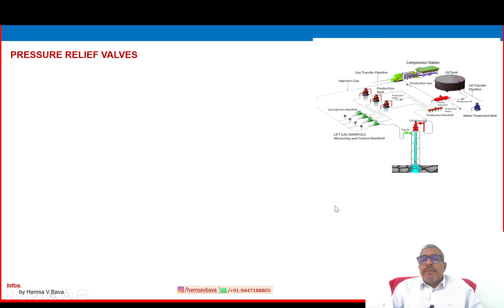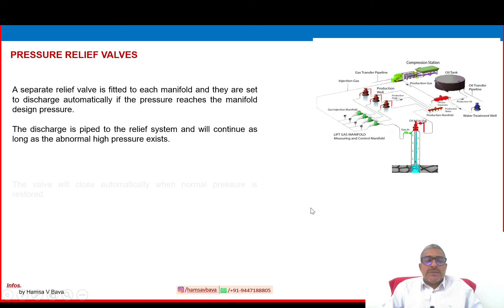Another one is the pressure relief valve. In the manifold, we generally connect a pressure relief valve, maybe more than one. A separate relief valve is fitted in each manifold and set to discharge automatically if the pressure reaches the manifold design pressure, to protect the entire downstream area. The manifold itself has a separate PSV, pressure safety valve. The discharge is piped to the relief system and will continue as long as the abnormal high pressure exists. This valve will close automatically when normal pressure is restored.